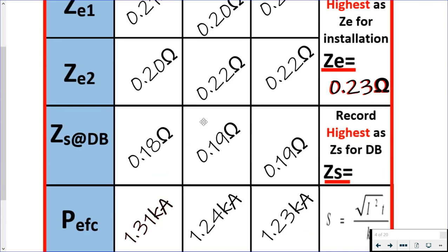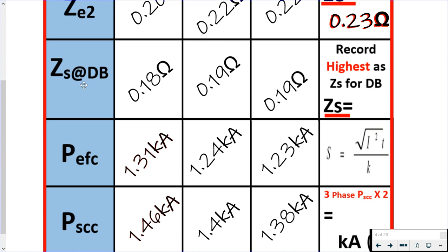We've then moved on after we've reconnected our earthing conductor and carried out our earth fault loop impedance at the DB and our prospective earth fault current. Depending on your meter, it may just show both values or you may have to have a function button to switch between the values, but it's the one test. For the earth fault loop impedance at the DB, our highest value that we've obtained here is 0.19, and that's what we would record on our test result sheets as the Zs at DB.